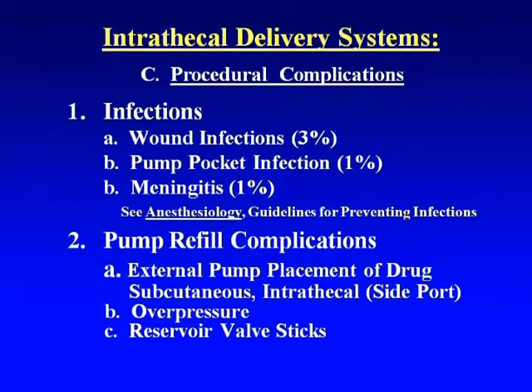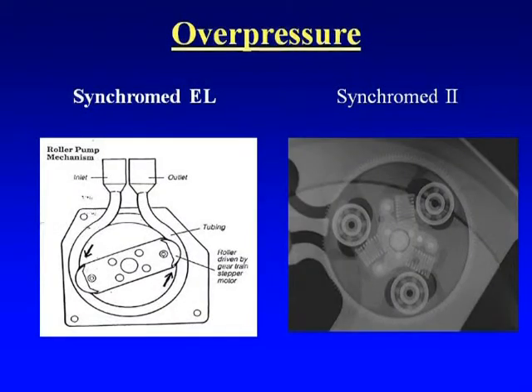Okay, overpressure, again, if you have your reservoir here and you fill it and you put in the stuff very rapidly and you cause a lot of pressure within the reservoir chamber, then you put pressure into your system here, and it can bypass the rotor because of this pressure and force itself out into the neuraxis.